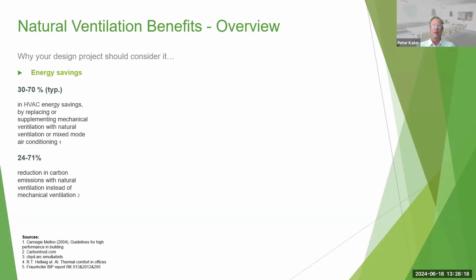So when the conditions become amenable to natural ventilation, the BMS will typically recognize this and hand over control to the natural ventilation system, and at the same time shut down the mechanical ventilation system so that natural ventilation can take over. And then, of course, when the conditions become unsuitable, the natural ventilation system will hand control back to the BMS and stop operating the windows. You can get anywhere between 20 and 70% reduction in carbon emissions, and this is associated with the mechanical ventilation system energy use. So that's another big reason why the energy savings benefit is very important for the environment, especially.